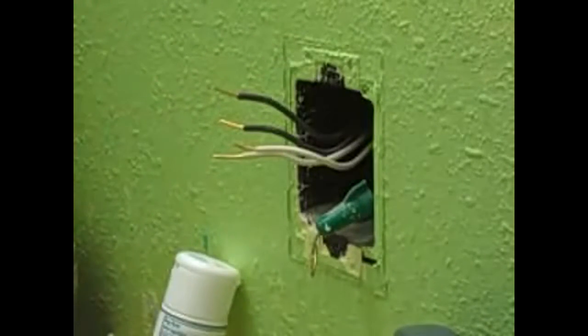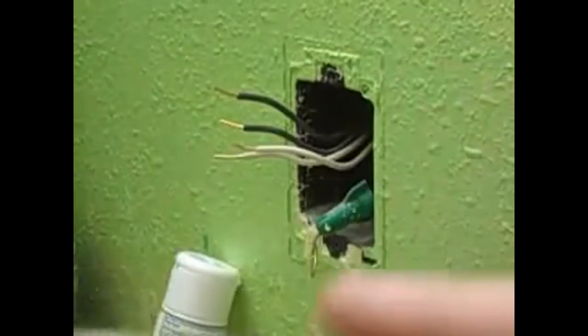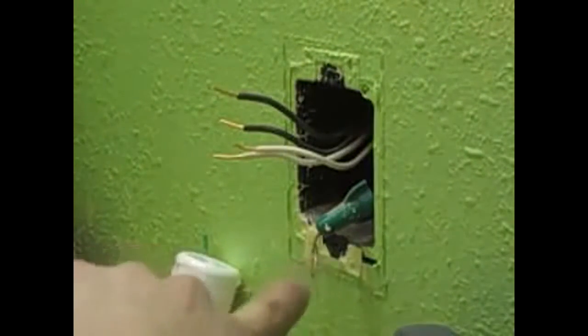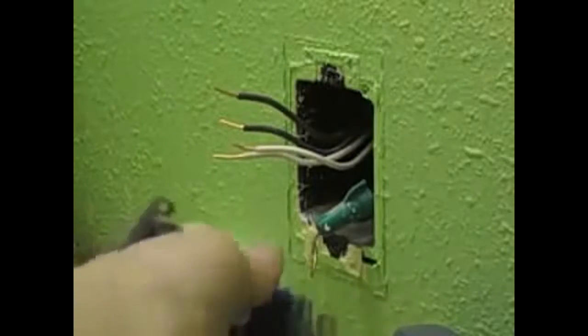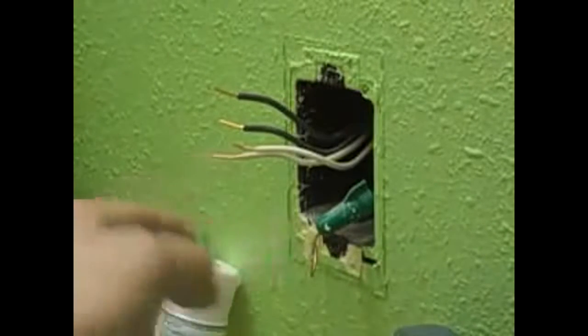Once you've stripped 1/8 of an inch off all 4 electrical wires, or in some cases 2 wires (a hot and a neutral) if you're at the end of your electrical circuit, but I'm in the middle because we've got 4. On your outlet, you'll have a green screw here, which is your ground wire screw. Take this wire and attach it to that screw. Make a loop with the wire cutters, loop it around, and tighten it down, and that's our ground.